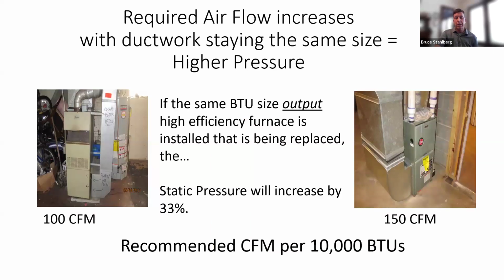So here's an example of that. This is kind of rough numbers, but the furnace on the left required about 100 CFM per 10,000 BTUs. And the one on the right is 150 CFM. So if you think about that, if someone came and matched the output of the furnaces and said, we're just putting in the same, but it's a high efficiency, we would have more pressure in the system. Now, one way to think about this is take a straw and blow into it, but now you put a very large blower on that straw and try to get the air through there. The pressure goes up. Pressure is not a good thing. It's like blood pressure. We're going to talk about that a little bit later, but we've got to be careful when we install new systems.